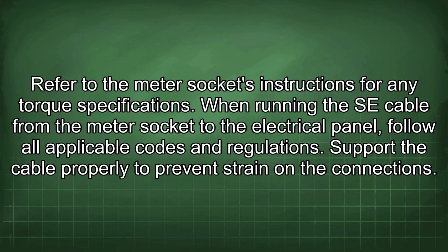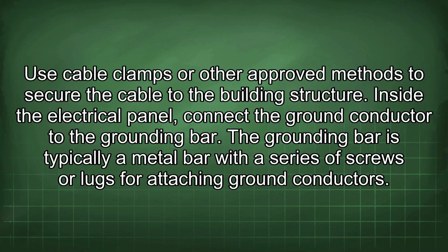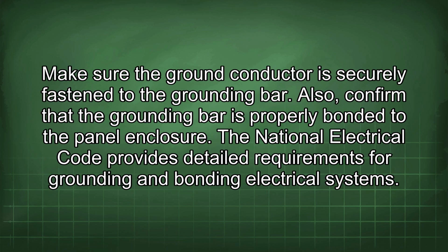Refer to the meter socket's instructions for any torque specifications. When running the SE cable from the meter socket to the electrical panel, follow all applicable codes and regulations. Support the cable properly to prevent strain on the connections. Use cable clamps or other approved methods to secure the cable to the building structure. Inside the electrical panel, connect the ground conductor to the grounding bar. The grounding bar is typically a metal bar with a series of screws or lugs for attaching ground conductors. Make sure the ground conductor is securely fastened to the grounding bar. Also, confirm that the grounding bar is properly bonded to the panel enclosure.